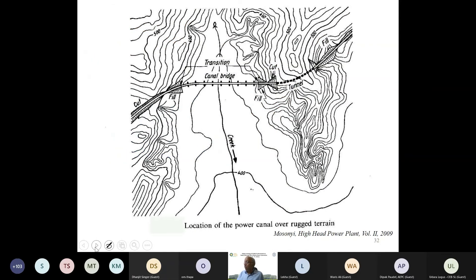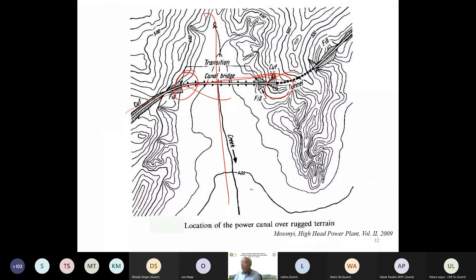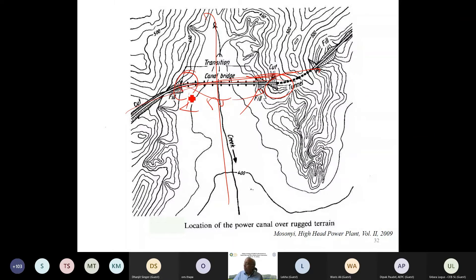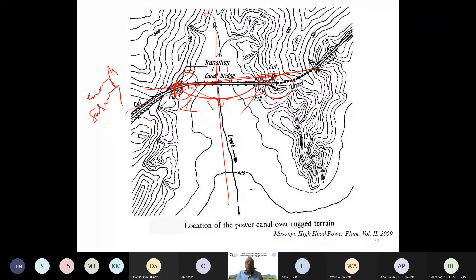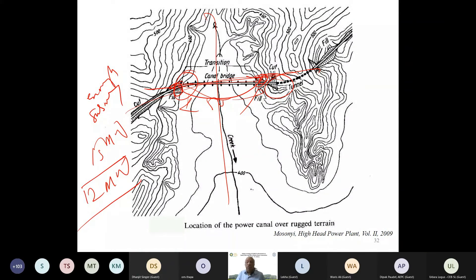When crossing rivers or drainage with a pipeline or aqueduct, hydraulic integrity must be followed. A cautionary example: a project in India near Bangladesh involved a 50-meter-wide river crossing. The pipe was not given enough submergence, so air entrainment and water hammer prevented the desired discharge from ever reaching the powerhouse. As a result, a 15 MW project has never produced more than 12 MW, even though all equipment and construction were of excellent quality.